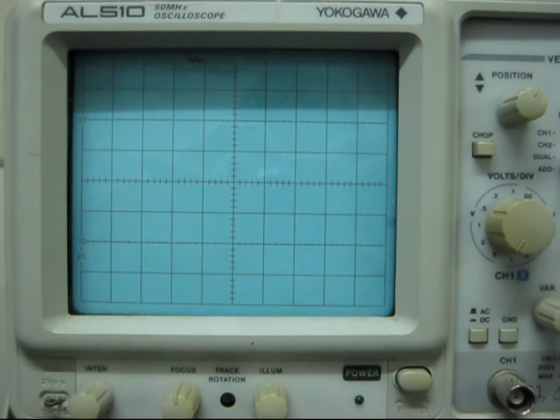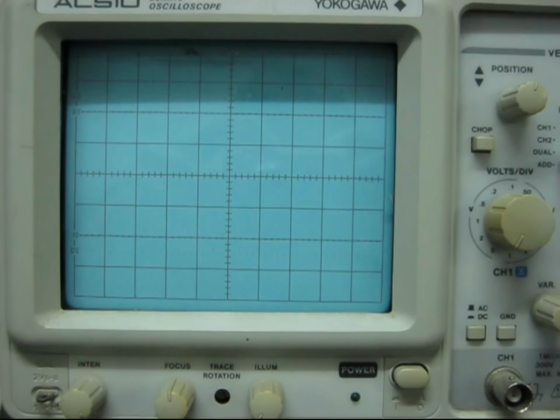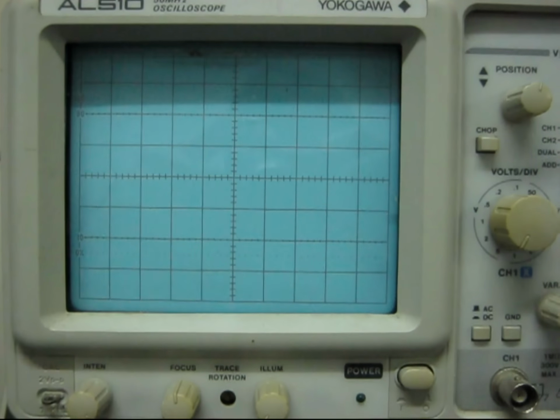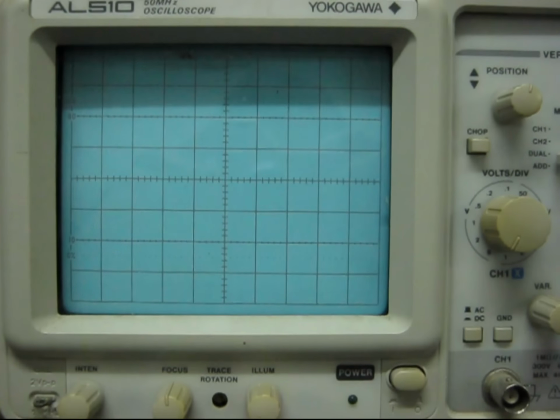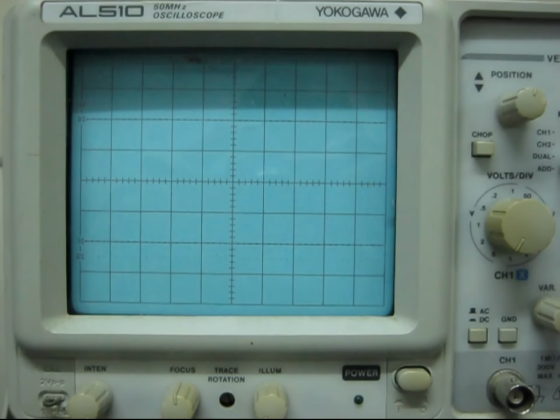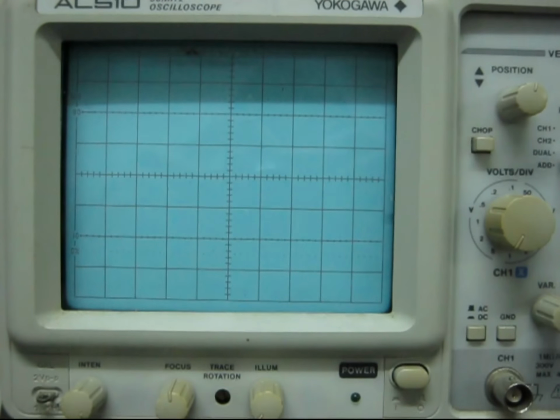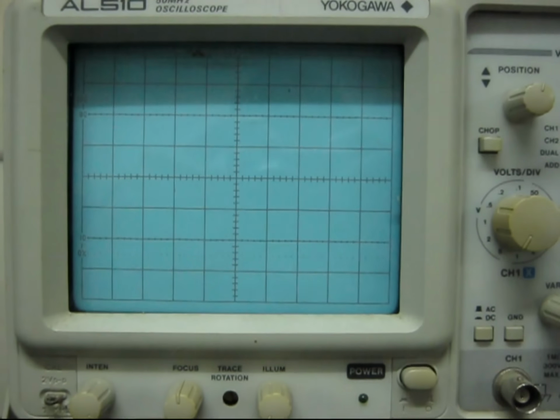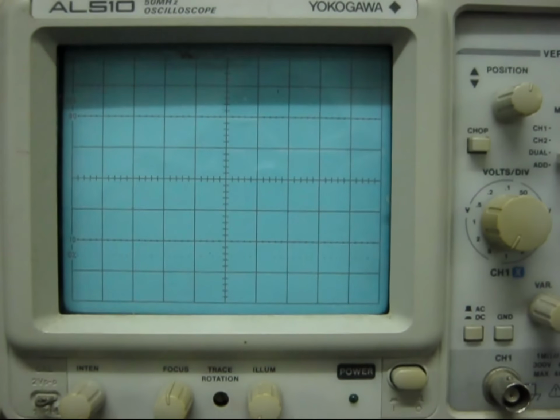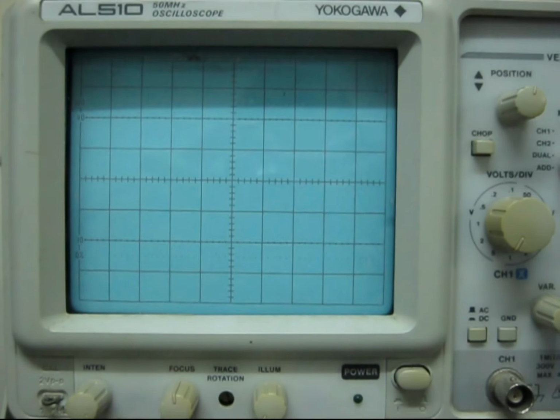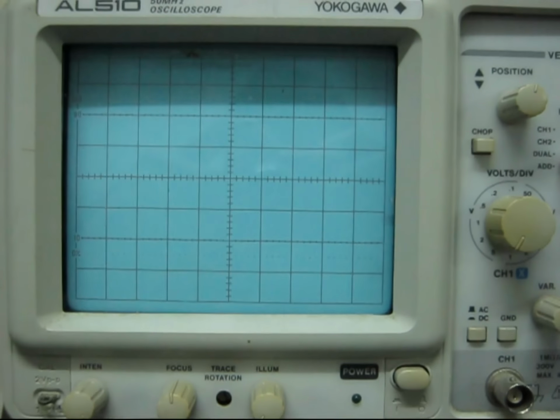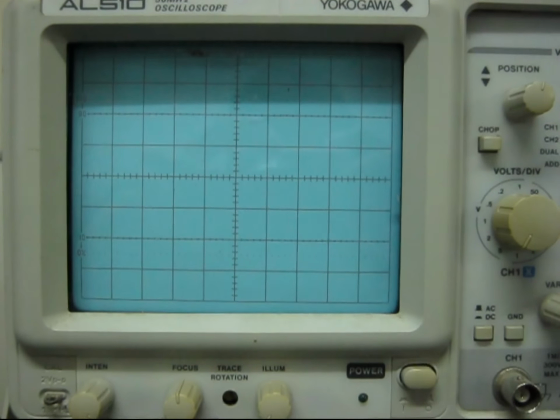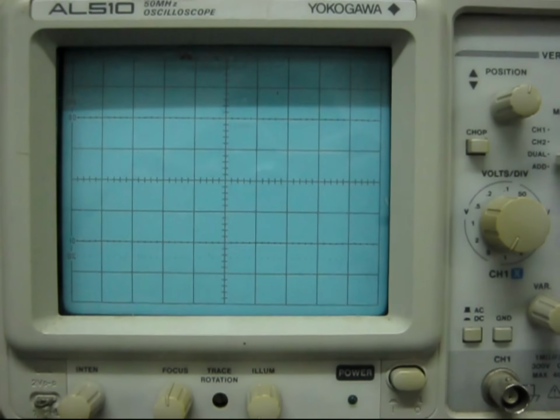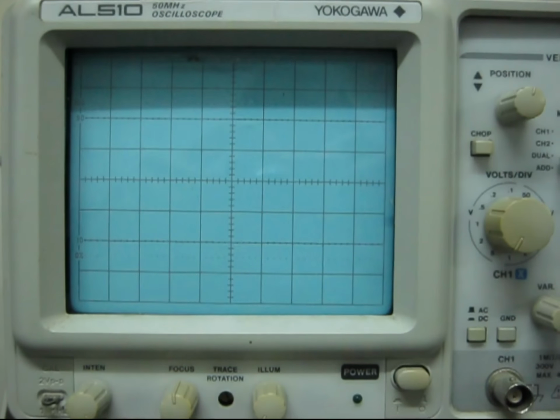For this segment, we will teach you how to use an oscilloscope. For the first step, turn power on. Once the power is on, it is normal for a power indicator or line indicator light to come on. Step 2. Wait for oscilloscope display to appear. Even modern semiconductor ones often need time for their electronics to boot up. Step 3. Find the trace. Usually the trace will become visible. If not, the beam finder button can be pressed and this will locate the trace.